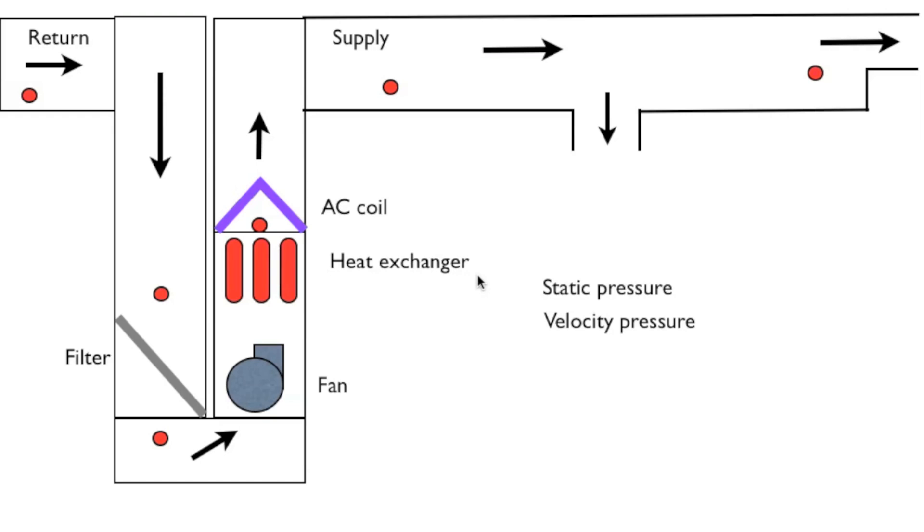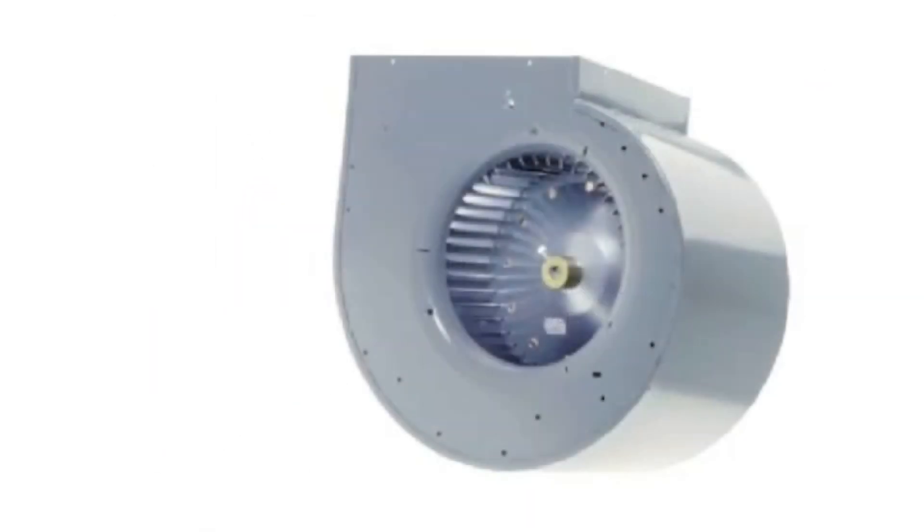The type of fan is important. We use what is called a squirrel cage blower. They usually look something like this. This is a direct drive blower - the motor's on the other side. The squirrel cage type blower is a static pressure blower.